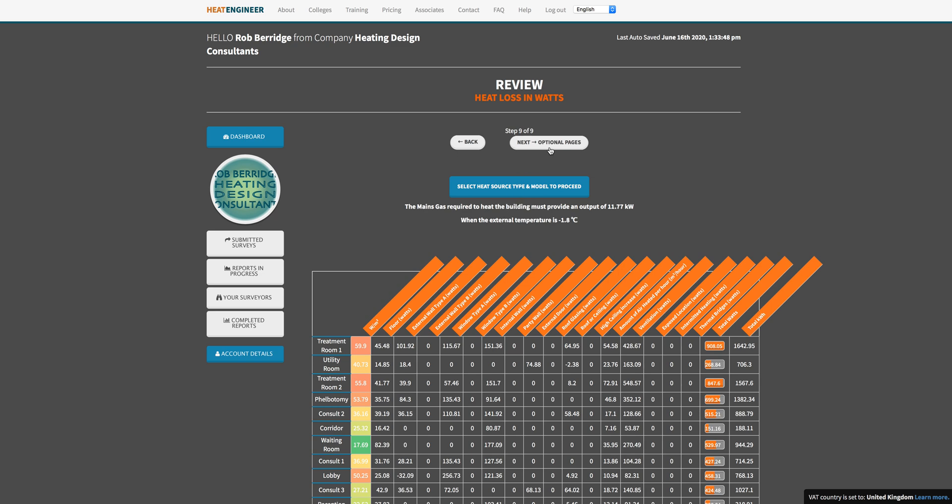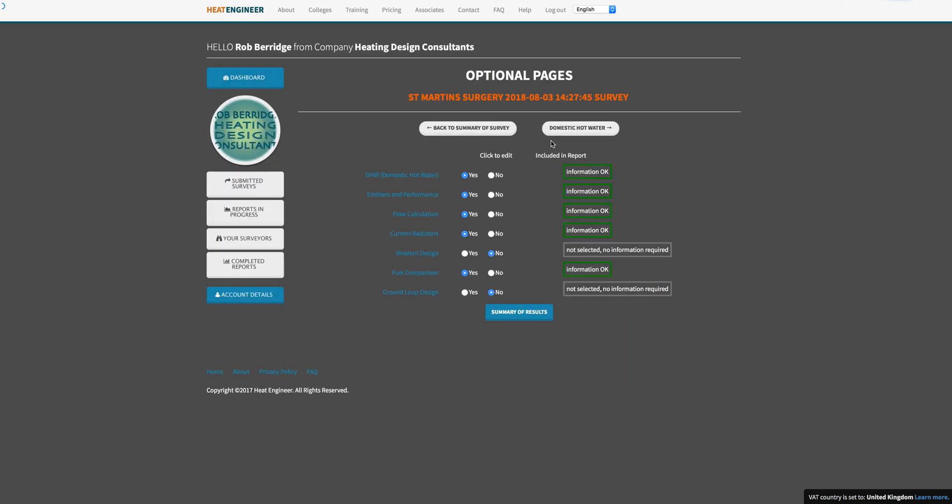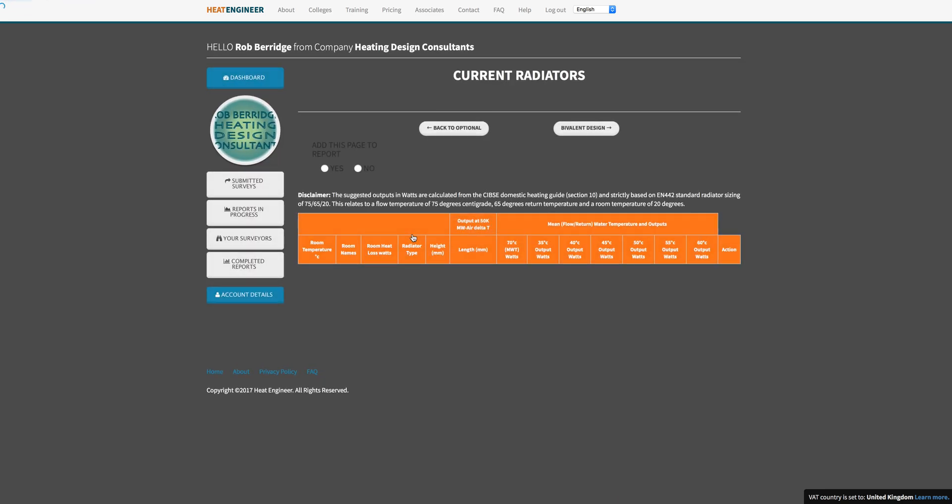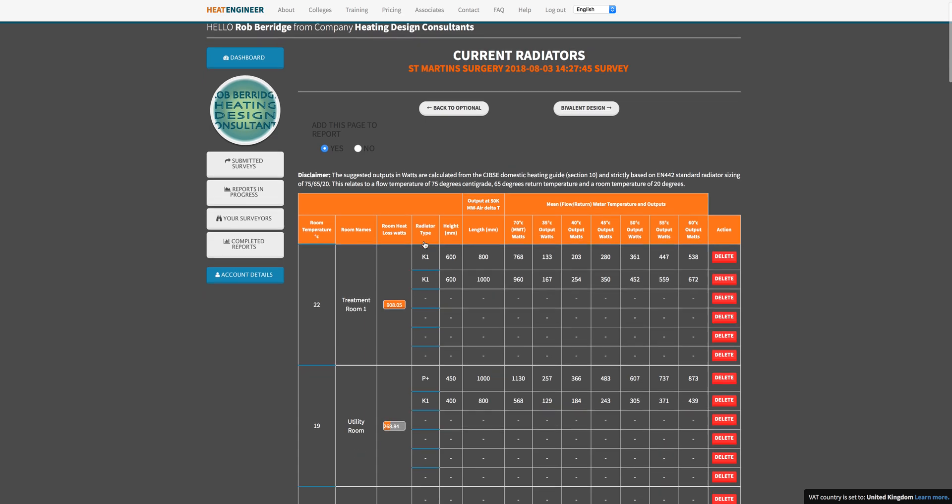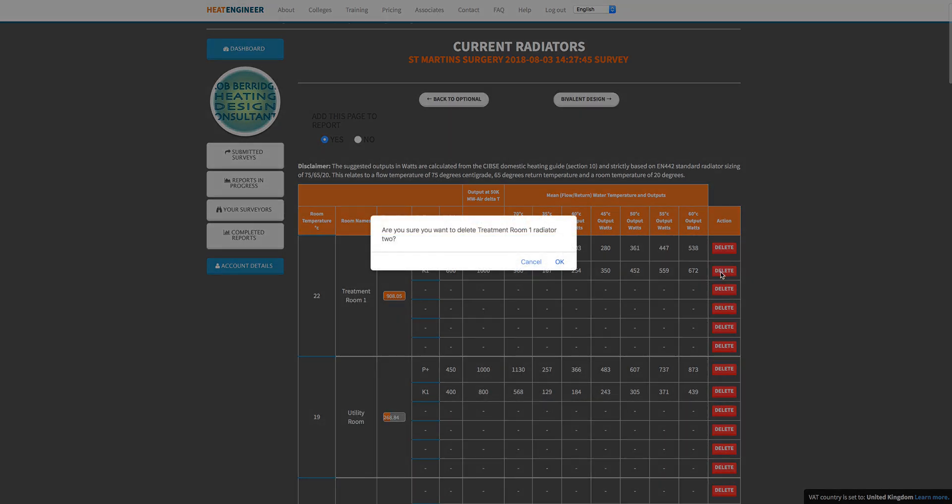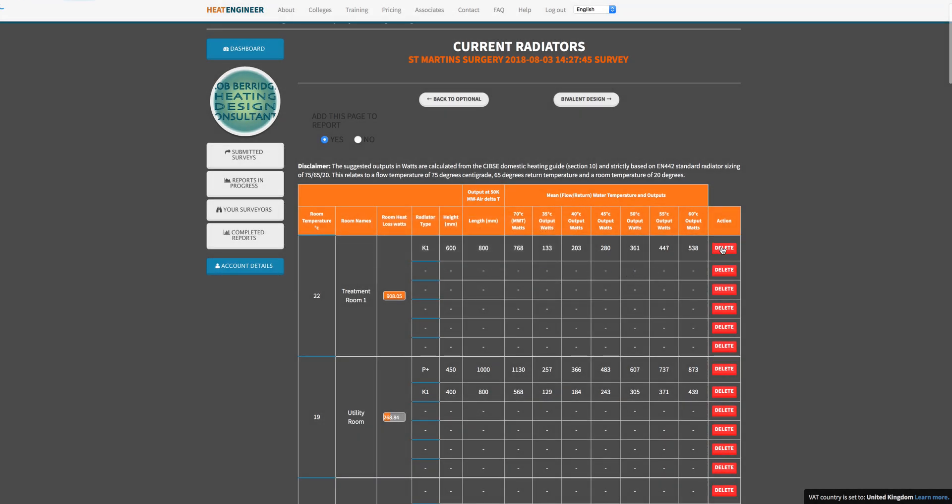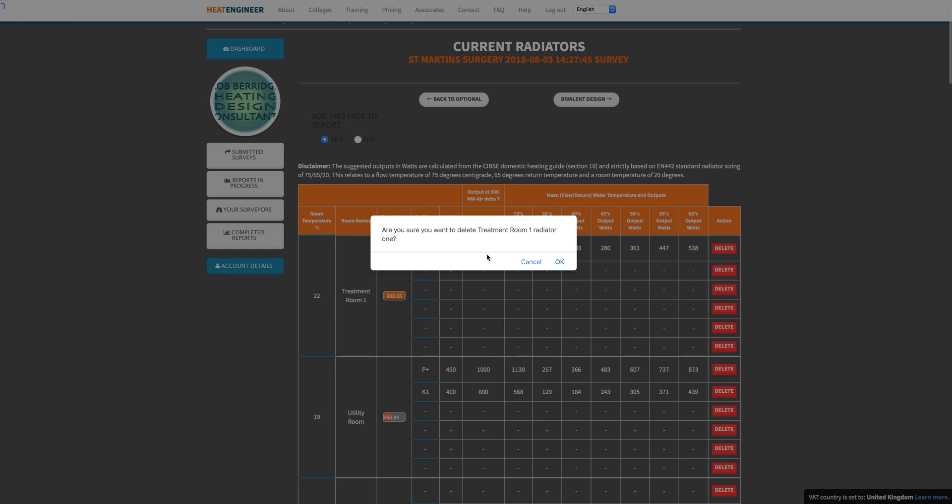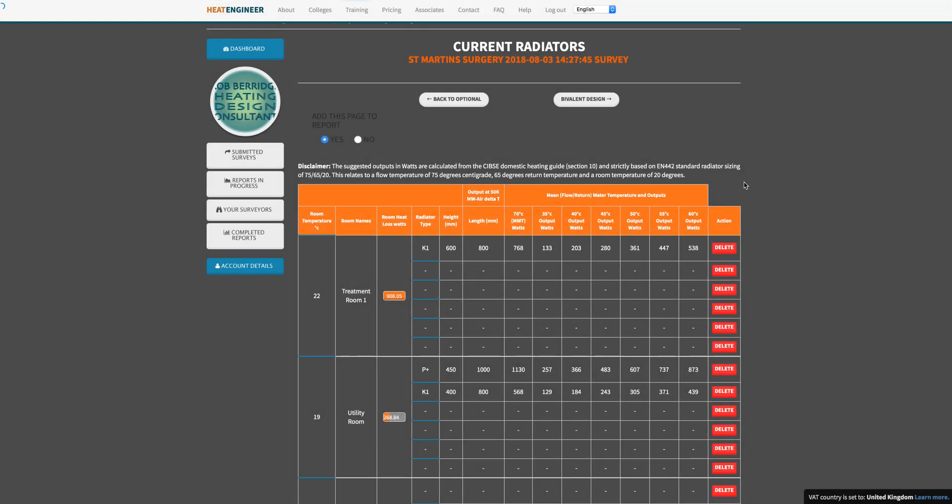Current radiators is something that is very difficult for people to understand and get correct. One of the biggest things is getting all the paperwork from various radiator suppliers at different flow temperatures. Now EN442, as many people would understand, doesn't work on flow temperature, it works on what is called mean water temperature. So if you had a flow temperature of 75 and a return temperature of 65, then your mean water temperature would be 70 degrees. Very important to understand that when you're sizing radiators. Let's delete these out of the way for the moment, and we can start again.